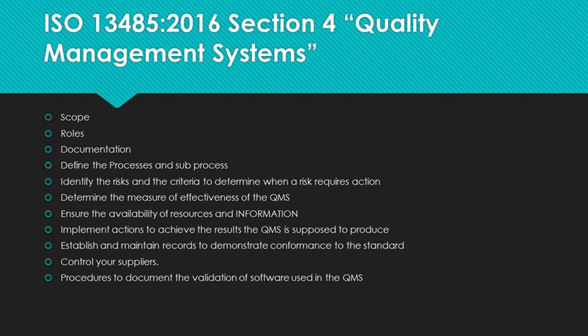How is documentation going to occur? What is the format — is it electronic, hard copy, in the cloud, video? How is it approved and modified? You have to consider and define the processes and sub-processes, and include the input and output to each sub-process and process, and the measurement method and interactions. You need to know if it's working or not, and if you change the processes, you have to measure the impact of that change on the process and on the device.